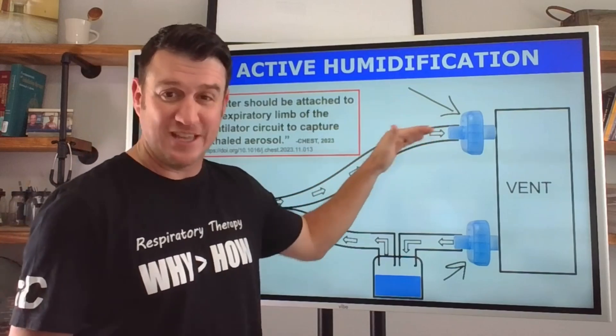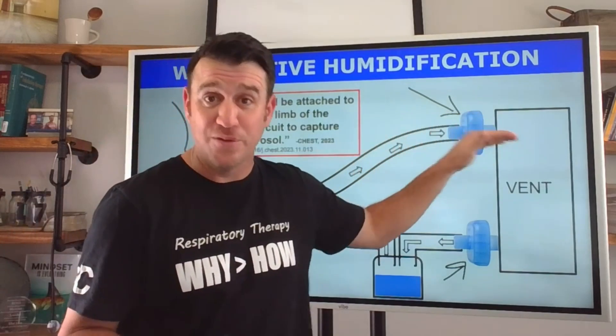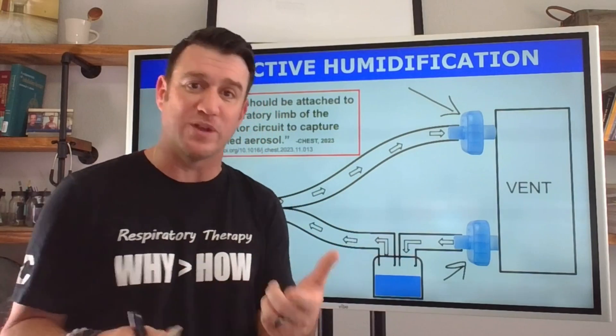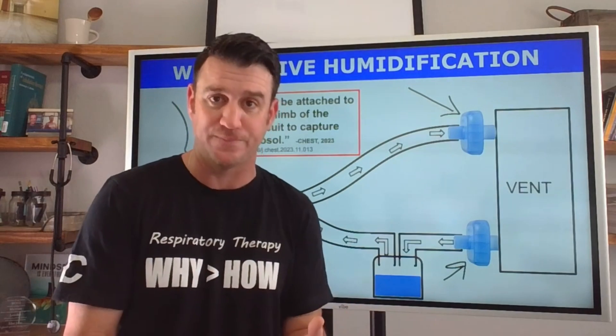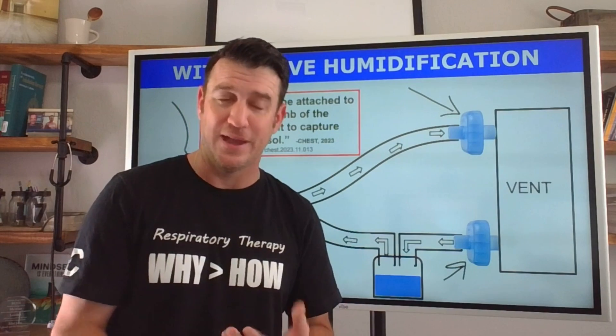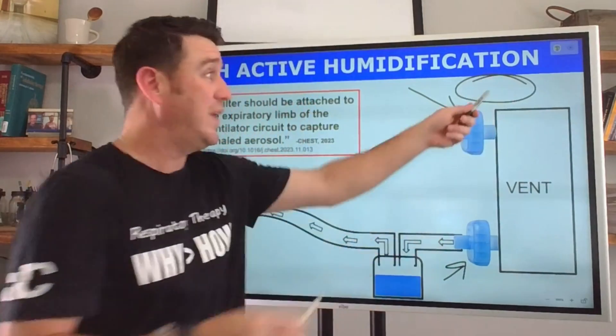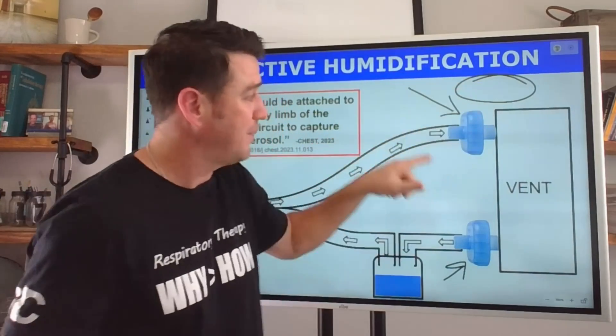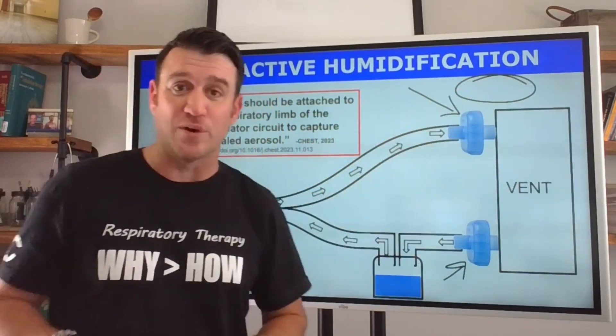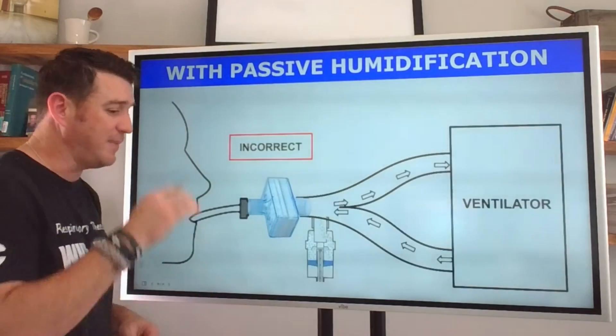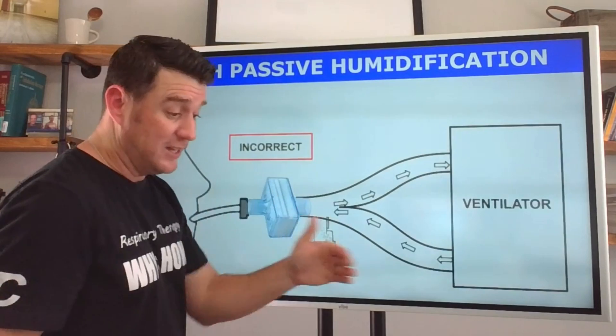An expiratory limb filter reduces environmental exposure and hazards associated with aerosol therapy during mechanical ventilation. It also reduces the amount of aerosol particles that return back to the ventilator that can impair and impede the accuracy of the ventilator in regards to pressure, flow, and volumes. Protecting the ventilator and the environment for which we exist in and for which visitors exist in is important, which is why an expiratory filter is valuable.